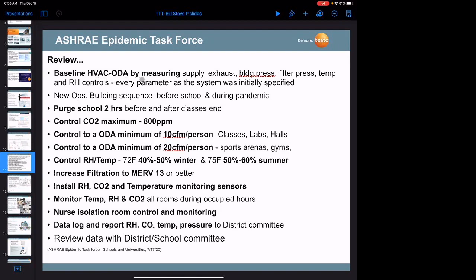So they want all schools to go back and remeasure all those values, compare them against how the building was designed, and see how far off you are. So in other words, before you start controlling this stuff, you've got to get the basics right. And to do that, we've got obviously Testo instrumentation to assist in measuring all these common variables that we speak about here. Next, once you've baselined and established that your system is working pretty close to the original specification, you want to change your building sequence.